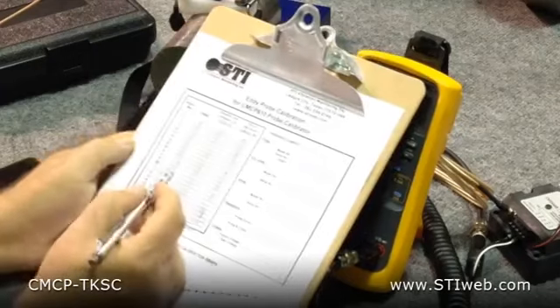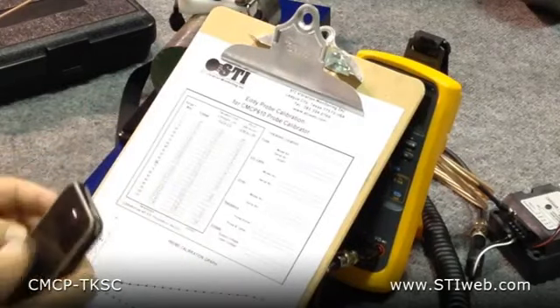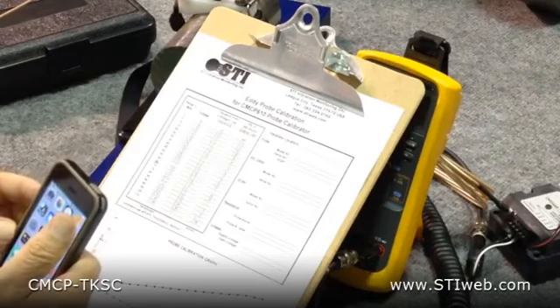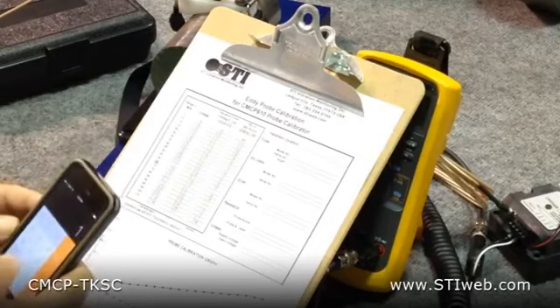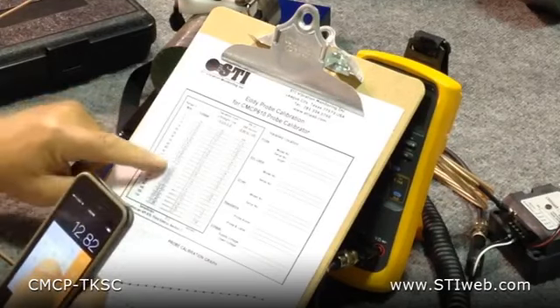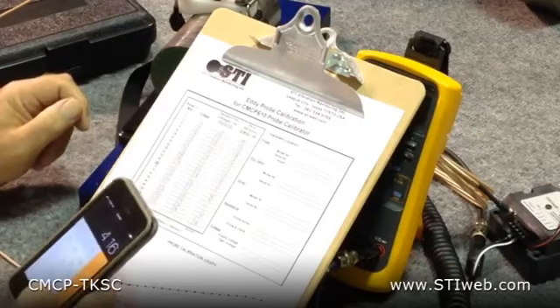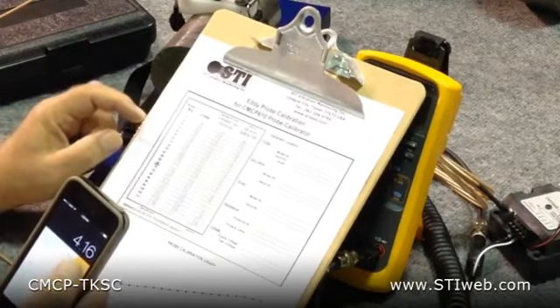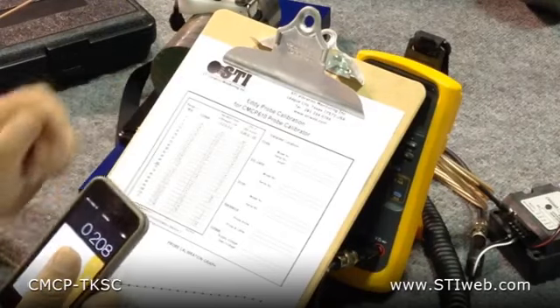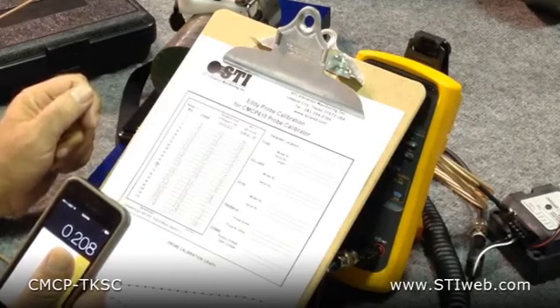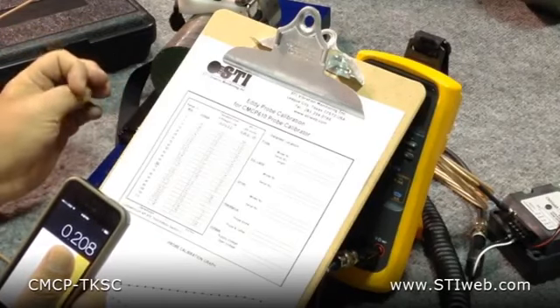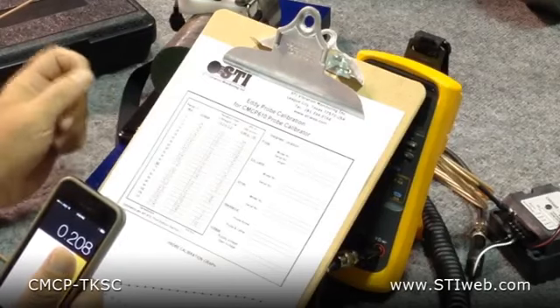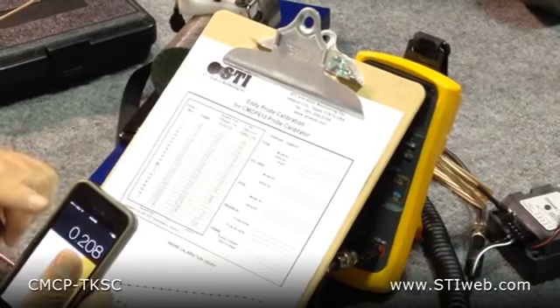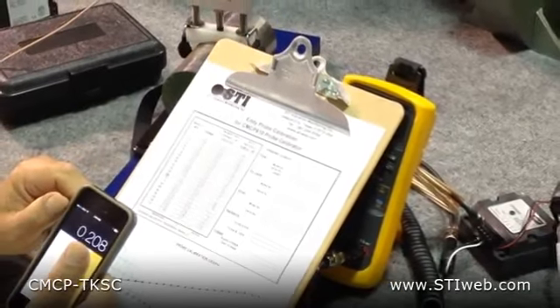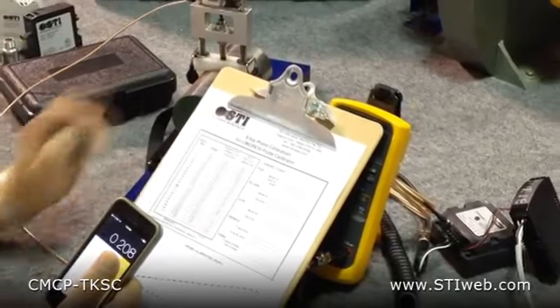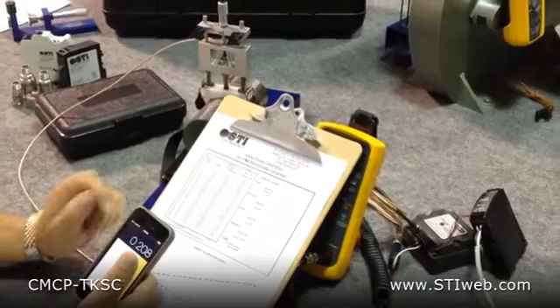And what you see here is at 65 we have 12.82, so we're going to use a calculator. We're going to enter 12.82, and subtract 8.66, which leaves us 4.16 volts for 20 mils. So we divide that by 20 mils, and that gives us 208 millivolts per mil. Standard calibration for API 670 is 200 millivolts per mil. 5% is allowed, so that's 10 millivolts. So this is within spec. It would have to be over 210 or below 190 millivolts for it to be out of spec. So essentially we're looking at 4000 series steels, and we're dealing with a system that's in spec, and our calibration is 208 millivolts per mil.